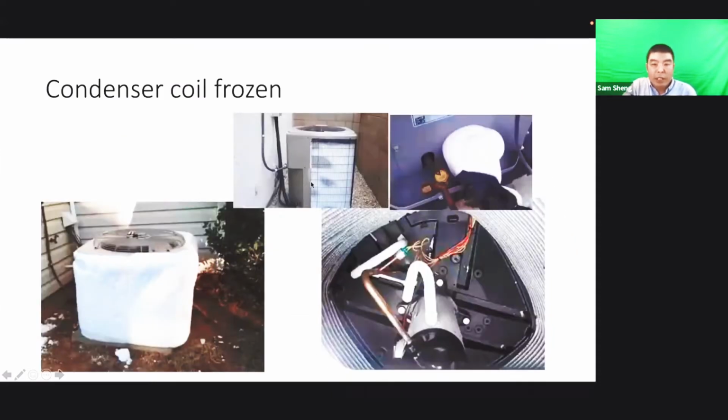Condenser. So okay, normally the frost or ice comes out on the outside, at the condenser unit like this, and the inside A coil must be iced too. Yeah, so we can see the frost or ice, and the connection here from the inside to the condenser unit is iced here.